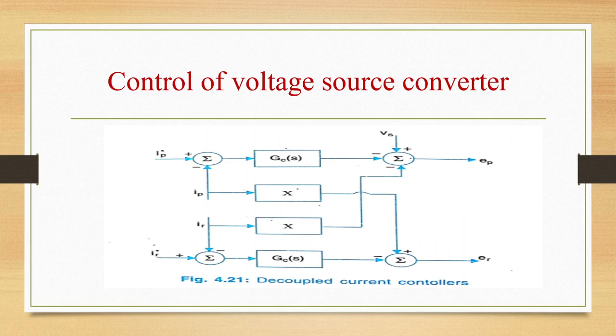PI controller time constant Tc can be chosen to cancel the poles introduced by the current flow in the inductive circuit. If Tc is equal to L by R and Kc is chosen as L by Ti, we can show here that IP equal to 1 by 1 plus sTi into IP conjugate, IR is equal to 1 by 1 plus sTi into IR conjugate. Value of Ti can be chosen to provide specified response time for the current controllers. In general, the response time is a fraction of a cycle.